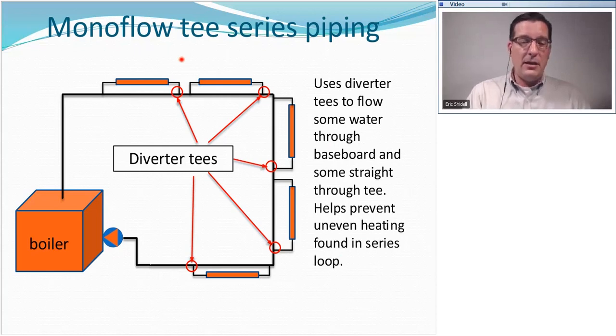Seeing them in commercial buildings is going to be less common than in residential, but hey, use your creativity out there and just about anything goes. So you've got to understand what the monoflow system is. The monoflow system consists of pretty much one main loop of pipe that runs around the whole perimeter of the structure. And coming off of that is a T, which will branch off, feed through a radiator, or feed through a baseboard, most likely, and come back into the main.